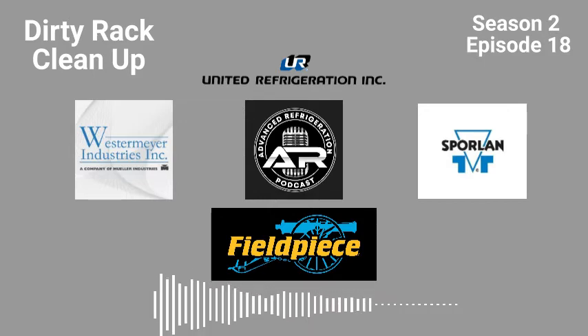The only way you can clean that up is with wax filters and just getting it all out, pulling things apart. We've had stores where we've had that issue before, and the only way we get it out is taking stuff apart and cleaning it. Major valves are where it gets stuck, it seems to get stuck in the discharge line and the drop leg for some reason. The drop leg holdbacks, I find those all the time gummed up like that, where they won't regulate or they stick. You'll find the port is all jammed up with that stuff. Just taking brake cleaner to it and cleaning it up, it seems to clean up pretty quick.